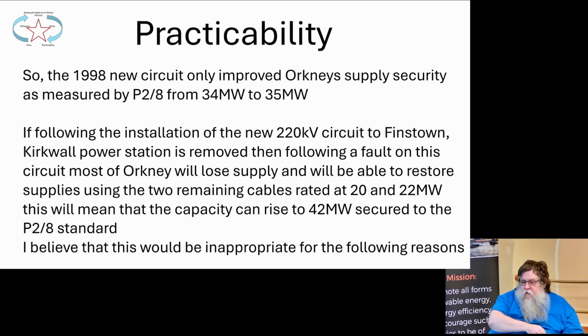So the new circuit only improved Orkney supply security as measured by P2/8 from 34 to 35 megawatts. A huge amount. The main reason wasn't to improve the supply security, it was to cut down on the amount of running that was being done at Kirkwall Power Station. And I think the last year we had the peak lop on about 200 days out of 365, so more than half the year we were peak lopping, which is quite significant.